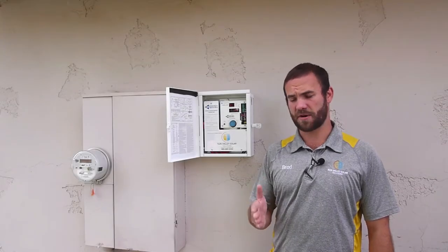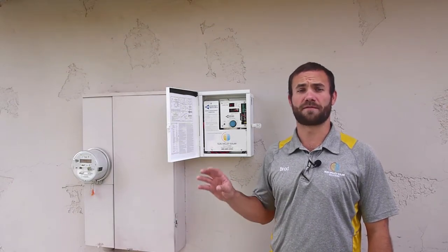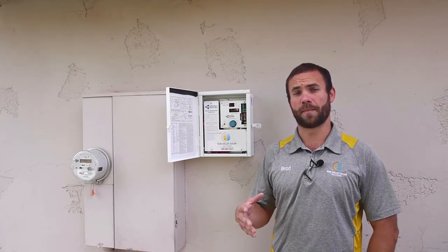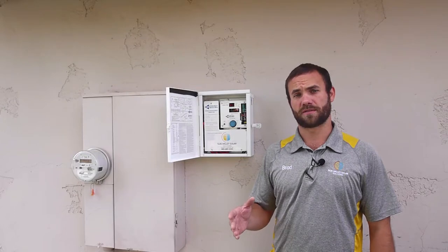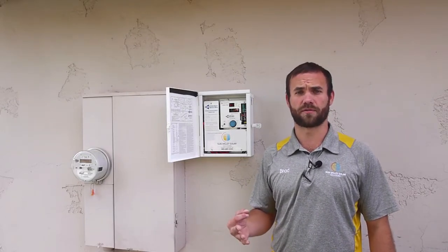Monday through Friday. What SRP is doing is they're taking a reading every half hour during those on-peak times to see how much electricity you're consuming from them. The highest amount of electricity you have consumed from them during any of those half-hour segments for the entire billing cycle is what that third demand charge is based off of. And we'll go into demand charge in just a little bit.